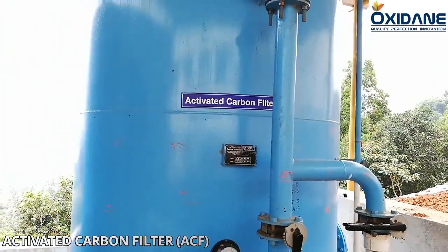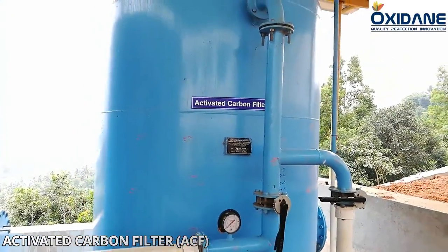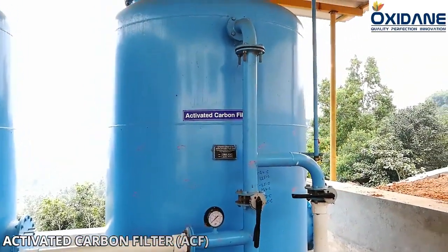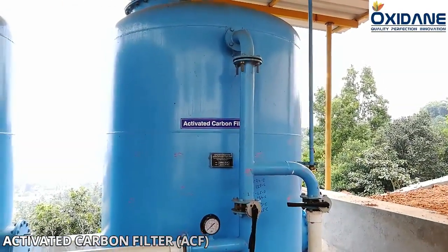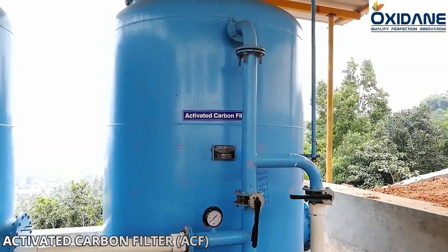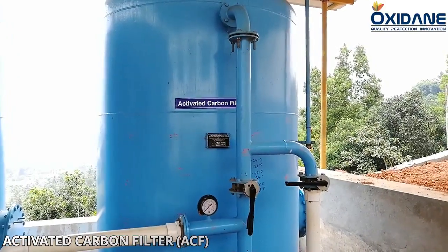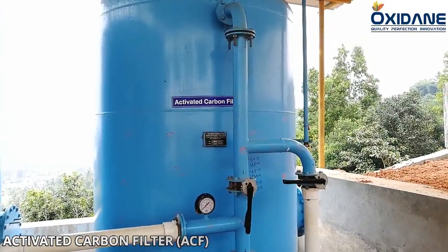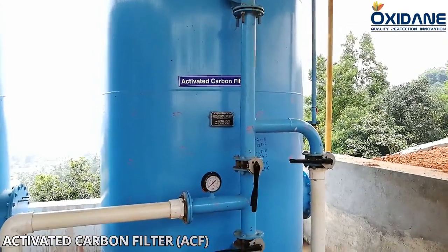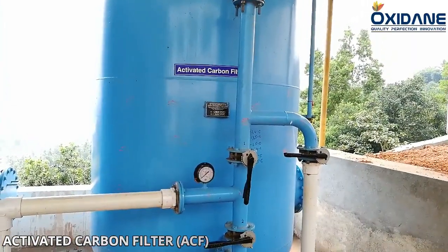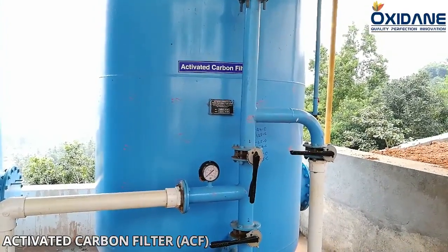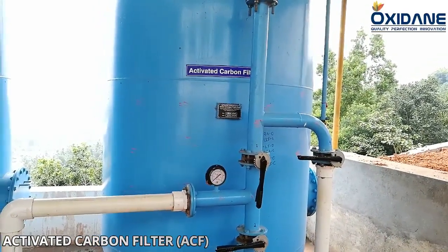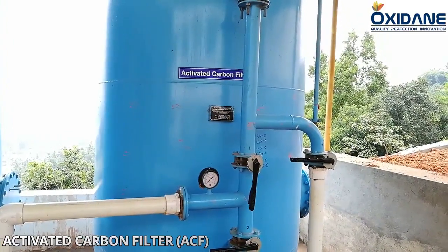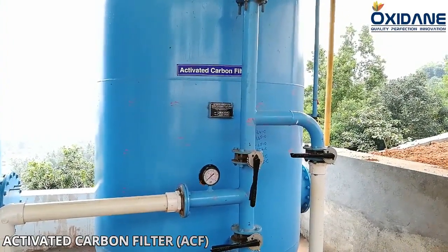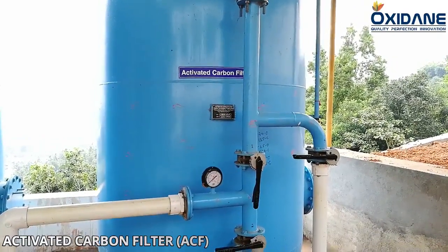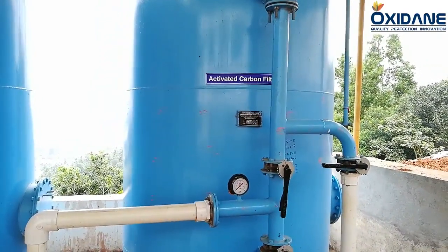It is designed to remove free chlorine, organic matter, odor and color present in the raw water and wastewater. Due to its high degree of microporosity, activated carbons provide a huge surface area. Activated carbon filter operates through adsorption. Adsorption is directly related to the surface area of the media. This great surface area furnishes a huge adsorption area for organic as well as chlorine molecules to attach themselves. The activated carbon filters consist of activated carbon granules supported by very fine quartz filter media. Various grades of carbon are used for specialized treatments.